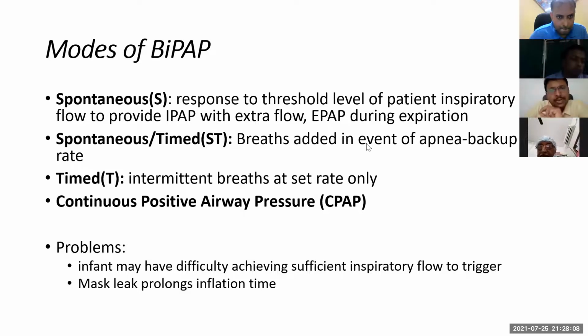Okay. Similarly, EPAP is during the expiration, where a certain amount of pressure will be maintained in the circuit, so the lung alveoli will not collapse. That is spontaneous mode. Expiration is not different in any of these modes; the only difference is in inspiration. Now, what is time mode? Even if the patient is not breathing, if you set the time mode, there will be a backup rate. If you set 20, that means every 3 seconds, 20 per minute. Every 3 seconds, one breath will be delivered to the patient, irrespective of whether the patient is triggering or whether the patient is able to initiate his own breath or not. The patient will be getting a breath every 3 seconds.